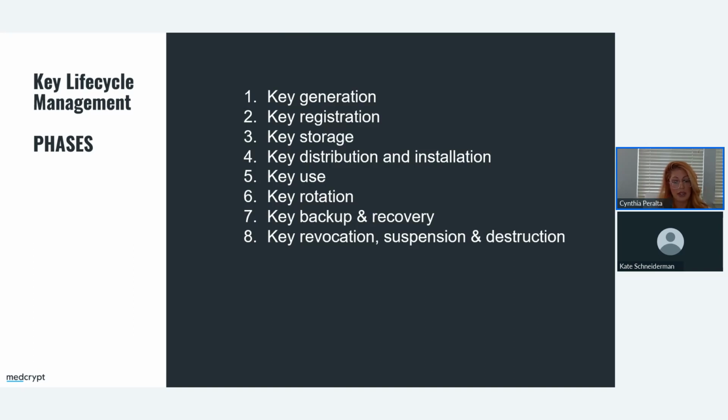The typical medical device encryption key lifecycle likely includes the following phases. We have key generation, registration of that key, the storage of that key, the distribution and even the installation of that key, all the way down to the use, the rotation, and even the backup and the recovery, which is very important. We'll talk about that later. And the revocation, believe it or not, and the suspension and the destruction of those keys at the end of life of the key.